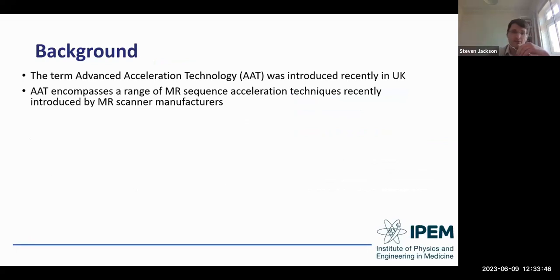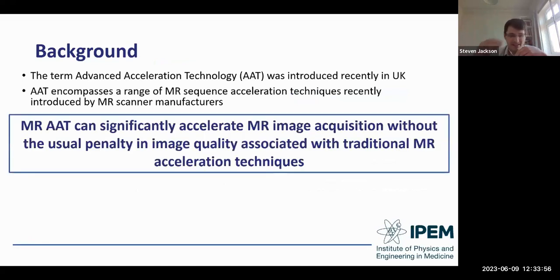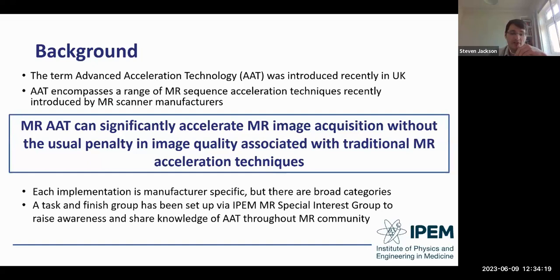The term advanced acceleration technology, or AAT, was introduced recently across the UK and encompasses a range of MR sequence acceleration techniques. The key headline is that MR-AAT can significantly accelerate MR image acquisition without the usual penalty in image quality associated with traditional MR acceleration techniques. Each implementation is manufacturer specific, but there are broad categories. A task and finish group has been set up via the IPEM MR special interest group to raise awareness and share knowledge of MR-AAT throughout the community.